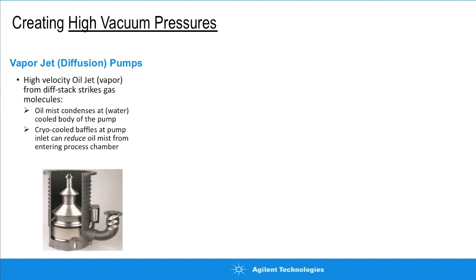The simplest type of high vacuum pump is the vapor jet or diffusion pump. This uses hydrocarbon oil heated to high temperature, which travels up the central channel inside the pump body and exits at three conical stages at around 750 miles per hour. Large hydrocarbon molecules strike background gas molecules, transferring momentum toward the edges of the pump. The oil condenses back to liquid via water cooling jackets, drips back down taking gas molecules with it, and those molecules are pumped away by a rough vacuum pump at the exhaust.